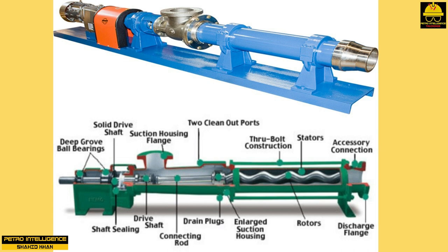Progressive cavity pumps provide high suction, extremely low shear, and smooth pulsation-free operation. These features are important where turbulence affects fluid composition. The PC pump is ideally suited for metering operations. Typically, this type of pump is used for heavy or viscous fluid service. The solid content of the process fluid does not affect the effectiveness of a PC pump. Progressive cavity pumps can be found in a variety of applications. Operating conditions include pressures up to 1000 psi, flow rates to 950 GPM, and viscosities of over 1 million centipoises.